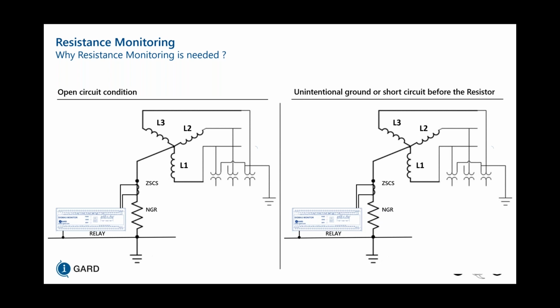So we have to look at what brought about the need for resistor monitoring in the first place. Well, in the past, what we used to do is monitor the current through the neutral to pick up the return path ground fault current that would be flowing through the resistor to be limited. Now, this was a good method up until a certain point where it was realized that the NGR was not even connected to the system. In this case, when the open circuit occurs, we've lost our system ground and our three phases are now floating, and this is an ungrounded system. This zero sequence current sensor here is not able to pick up any ground fault current because of this open circuit condition.